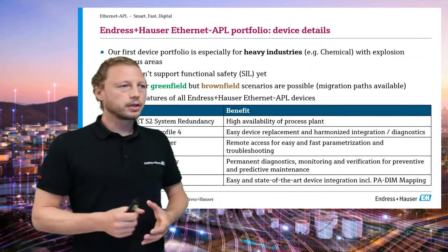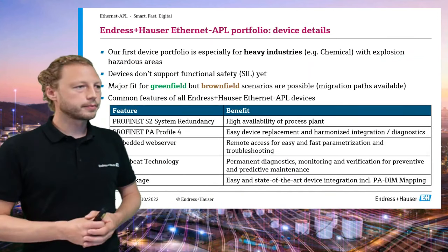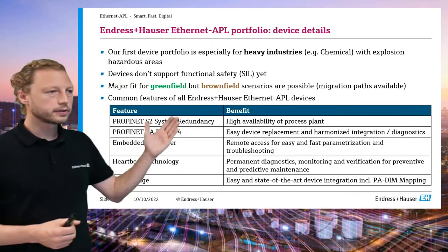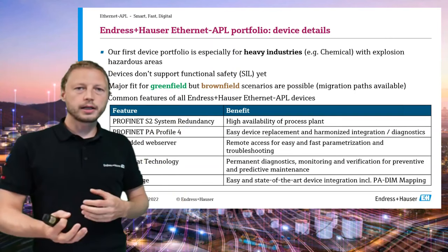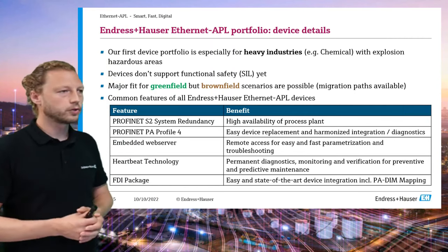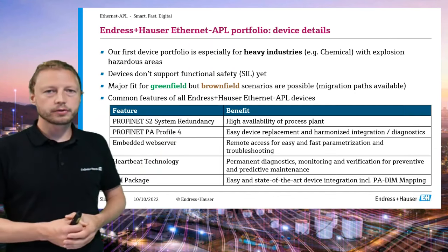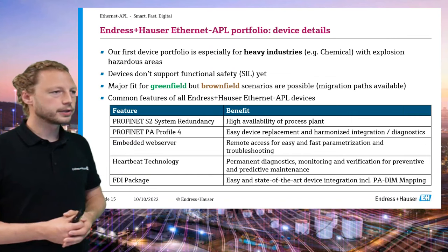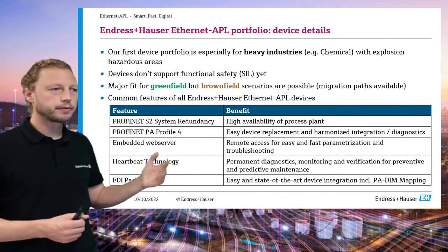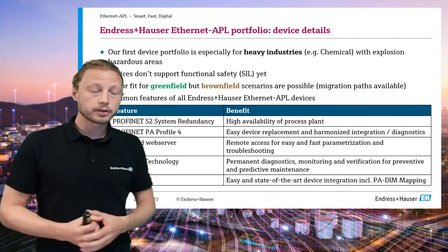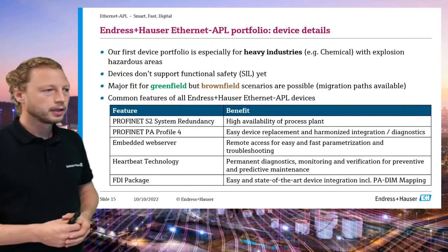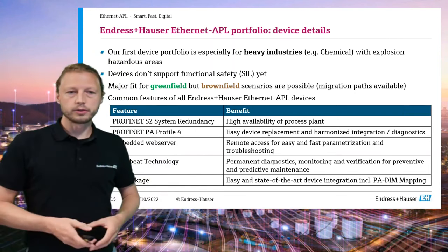Specifically for Profinet, these Ethernet APL devices will support system redundancy — the device can talk to two controllers so that if one fails, the backup automatically takes over without interruption. We are following PA Profile 4. Web servers are embedded. HeartBeat technology is embedded in all our products — contact us if you'd like to learn more about HeartBeat. FDI driver packages are ready as well.